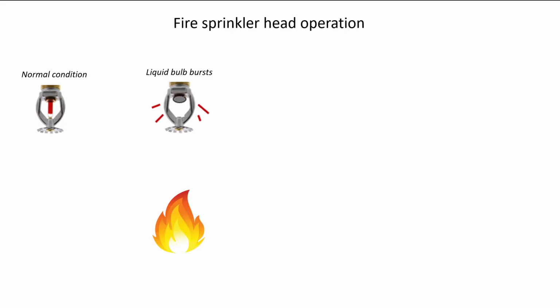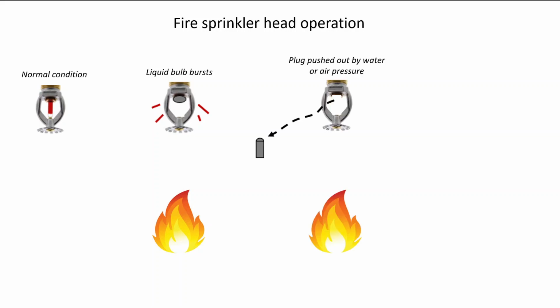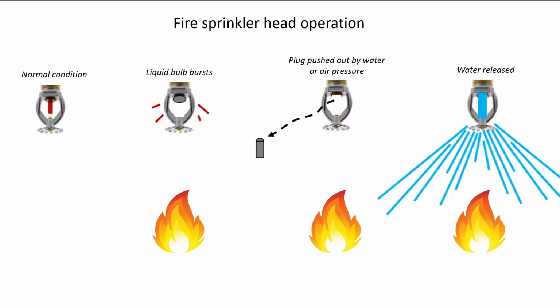If we take a look at the general operation, under normal condition, we should be able to see the glass bulb present in the sprinkler head. During a heat event or a flame, the liquid bulb will burst once the heat at the ceiling reaches that predefined temperature. The plug will be pushed out by either water or air pressure, and eventually water will be released over the ignition source, but only out of that one sprinkler head that is burst.